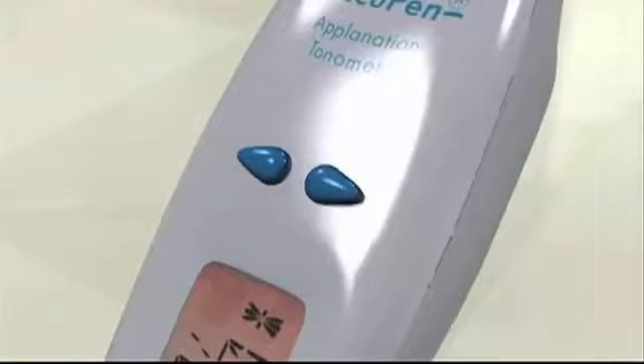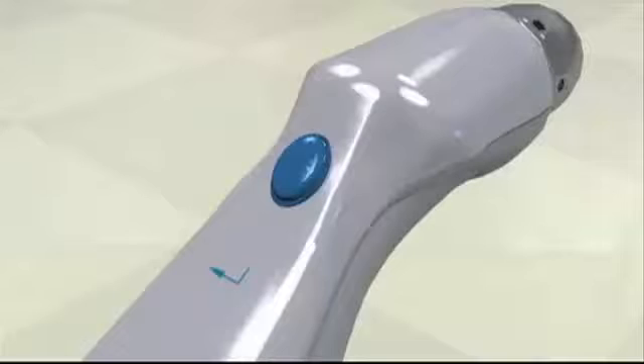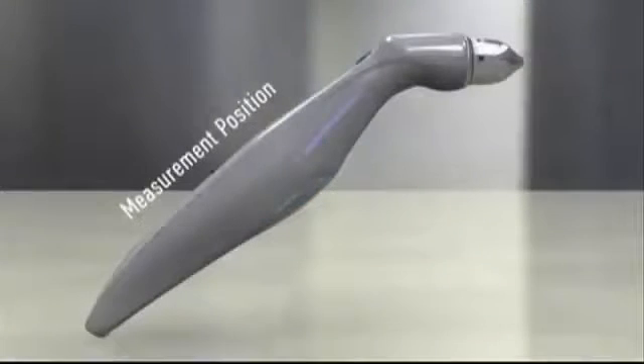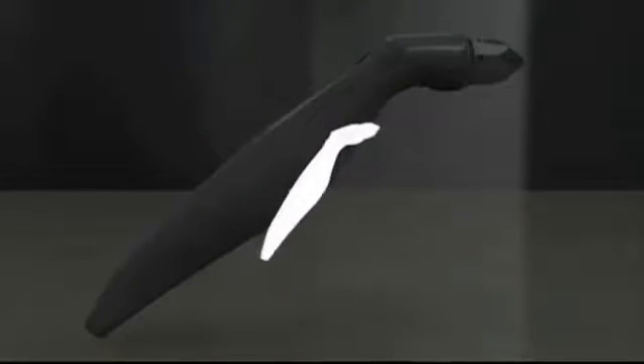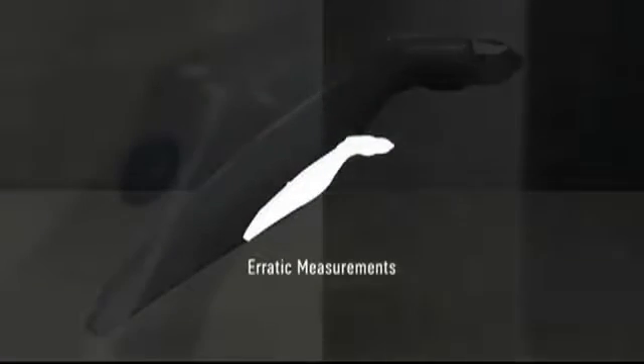To turn on your AccuPen Vet, press any control button. The product information briefly scrolls across the screen. The measurement screen will soon be displayed. To take a measurement, press and release the Action Control button. It's important to make sure the AccuPen is in the measurement position when this button is pressed. Shifting of the transducer tip from movement could lead to erratic measurements.